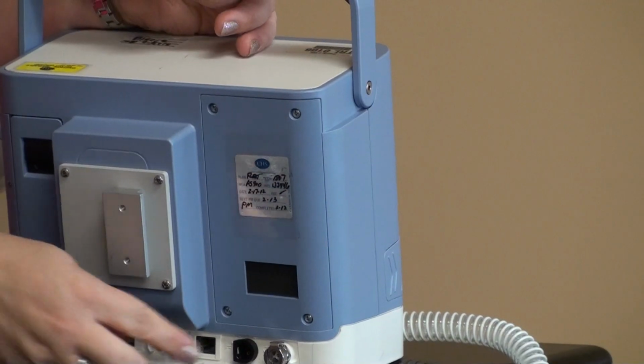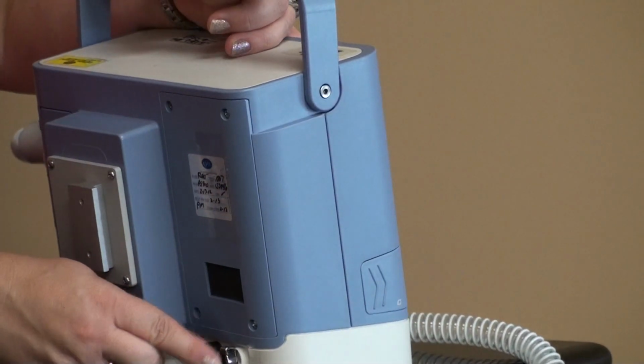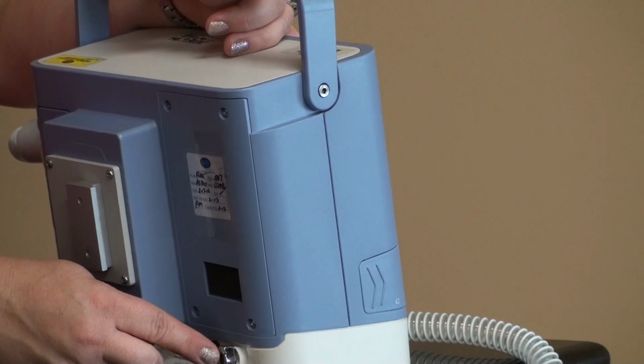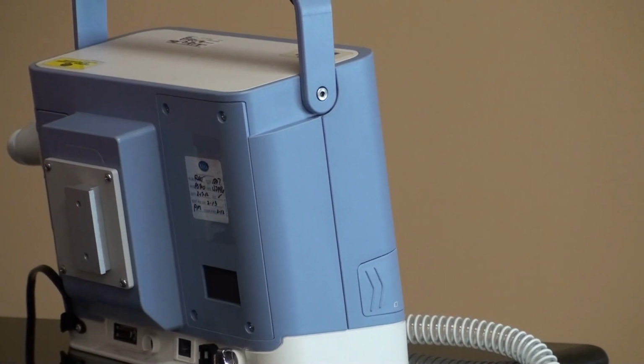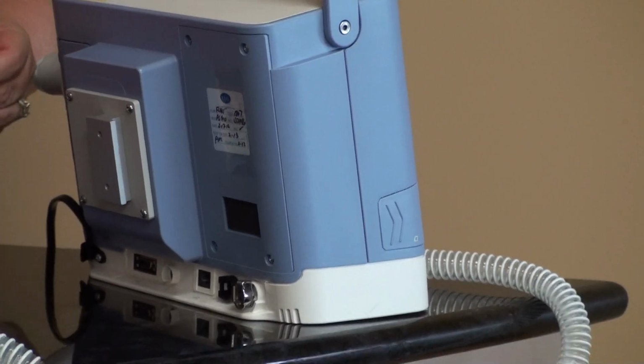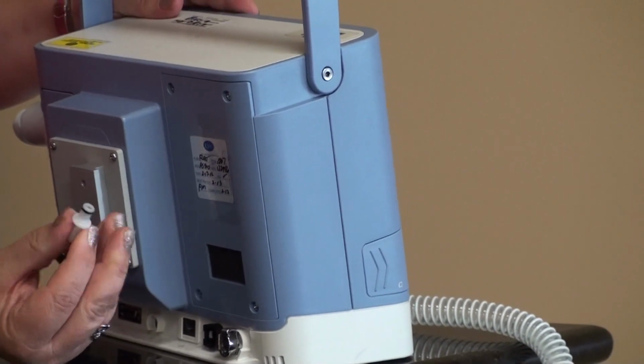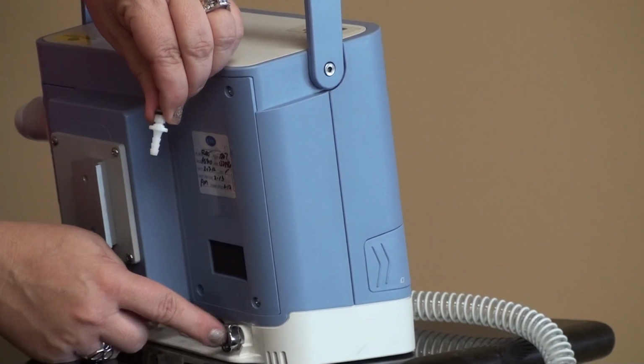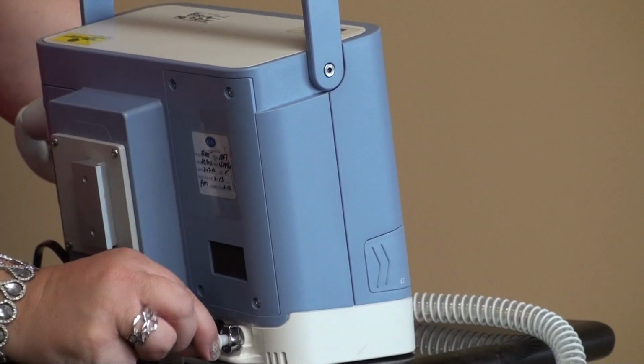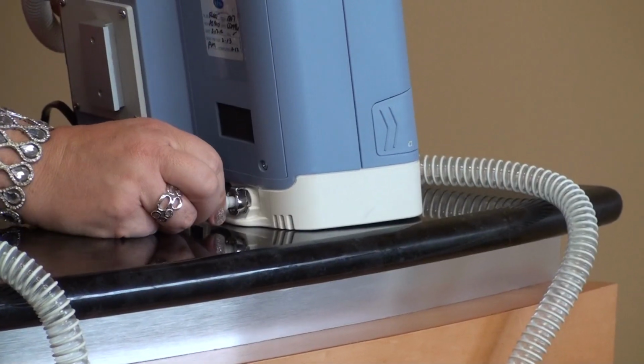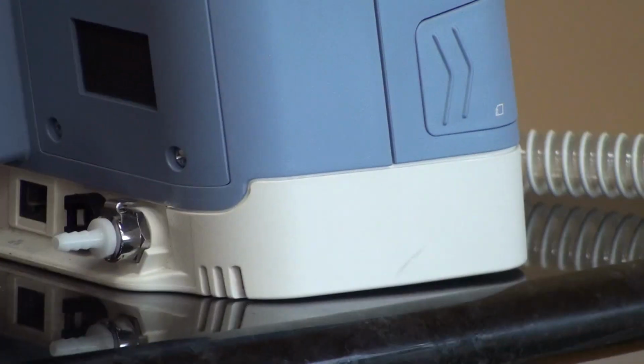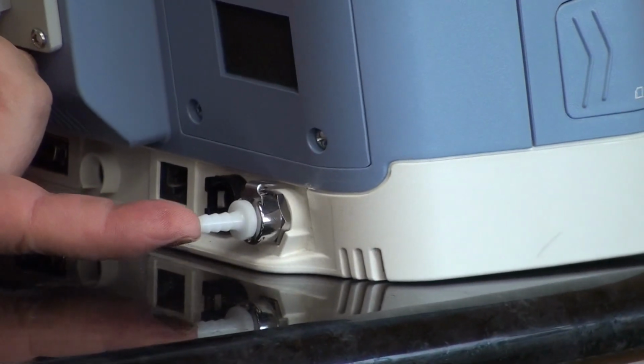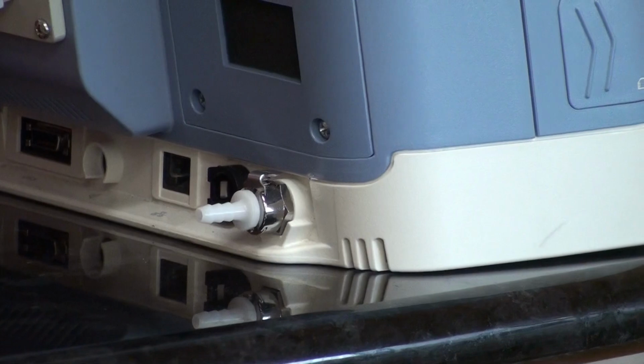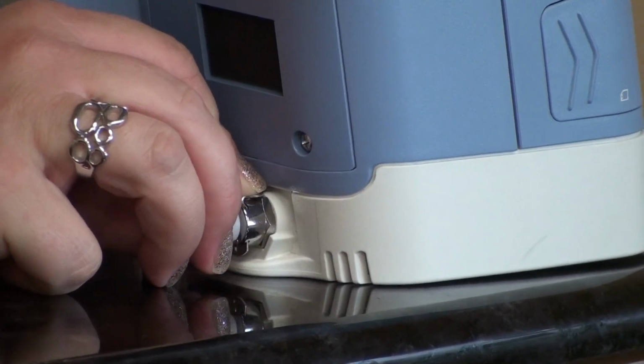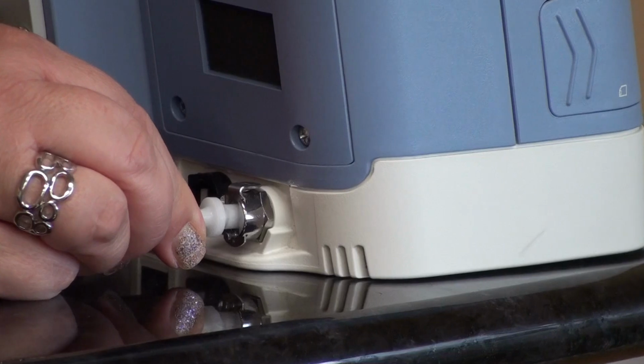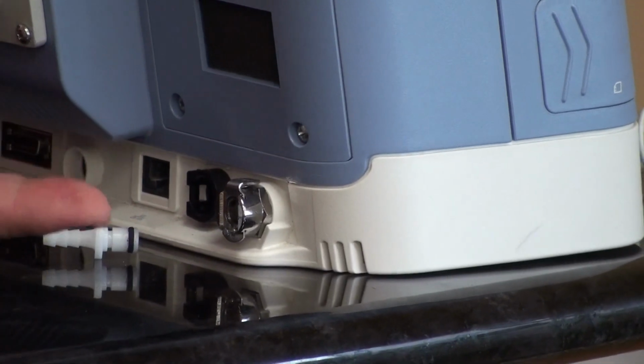The next thing on the back is your oxygen valve port, which will take flows up to 15 liters per minute. This is what I consider the weakest part of this ventilator because the piece that goes into it is made of plastic, a little white plastic piece here. And it does shove in there pretty hard. So when you're putting it in, make sure that it clicks. You'll hear that click. But notice my fingers have an indentation on it from where I pushed it in, because it is a hard push. To release it, you press down on the metal piece and pull out. As such. Again, indentations in my finger.